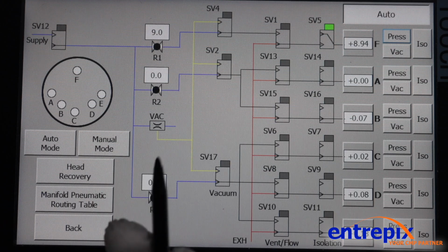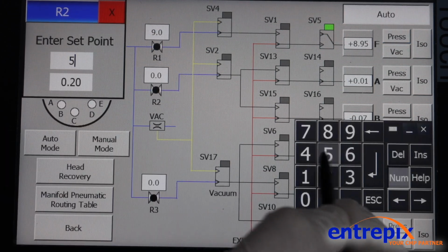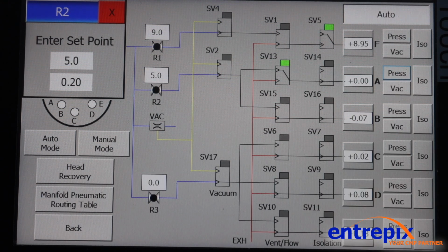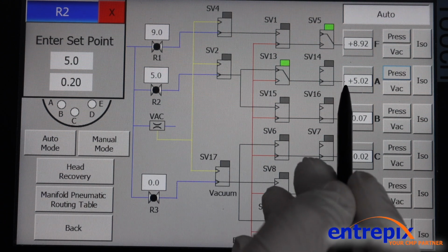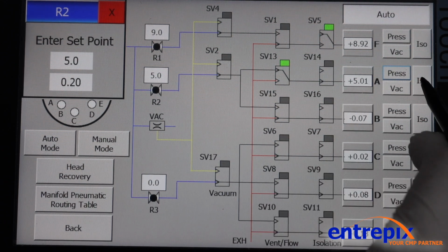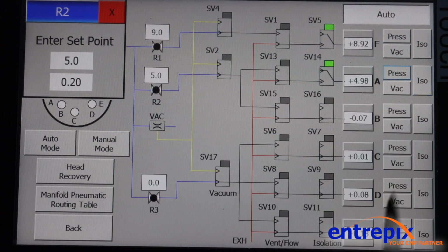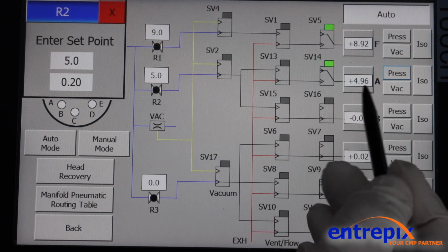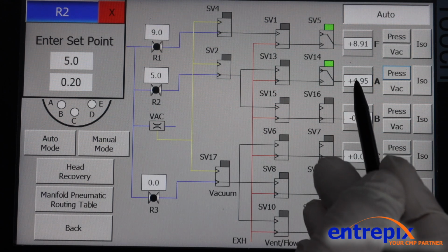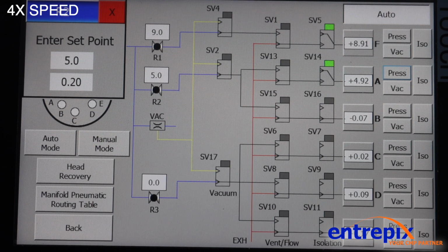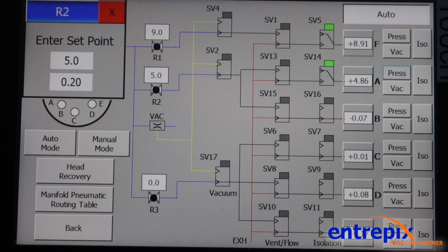Next, we'll test the membrane zone in the head. In this case, we will select a pressure of 5 psi and select pressure again to inflate the zone. As you can see, the pressure has reached the 5 psi and can now be isolated. Upon removal of the pressure and in isolated state, we can monitor this pressure falling rate over the next duration of 30 seconds. After the 30 seconds, you can clearly see from the isolated chamber that it is leaking with a passing of greater than 0.1, which is the limit. You know from this point that you need to troubleshoot the membrane section further within your head build.